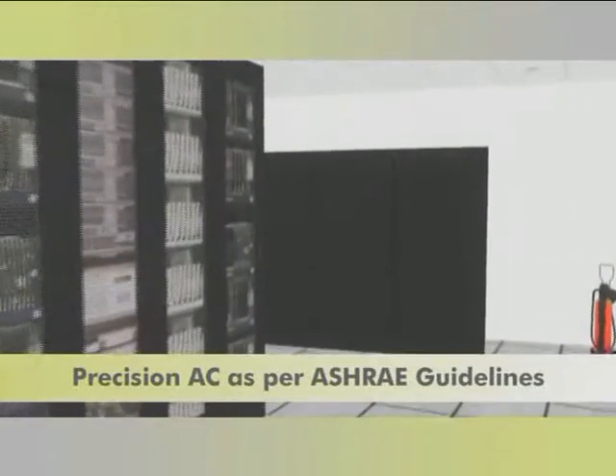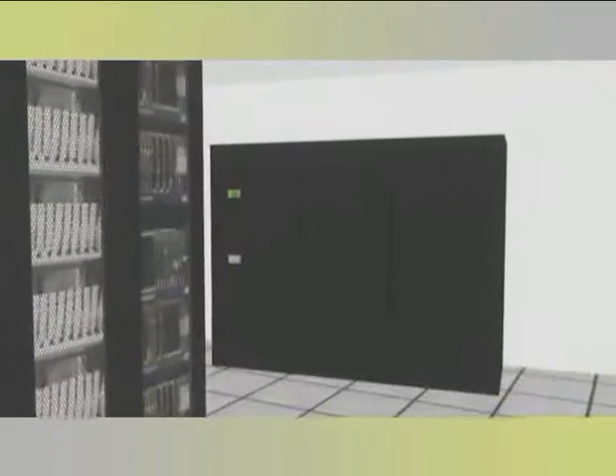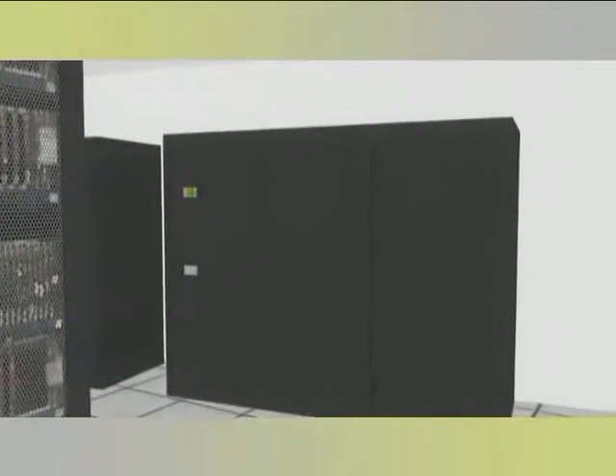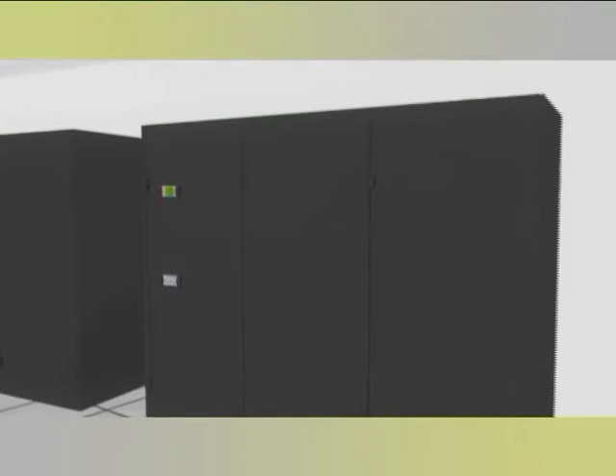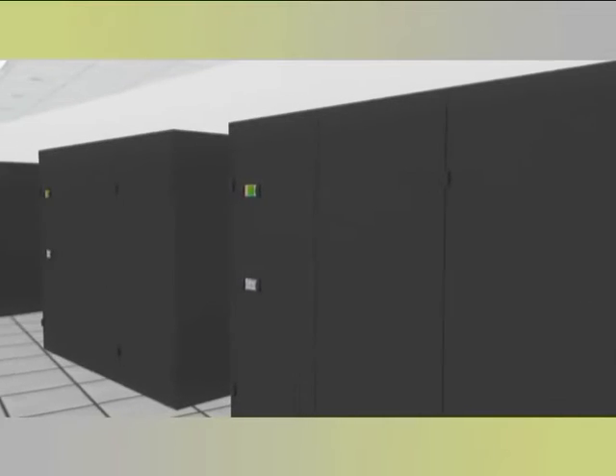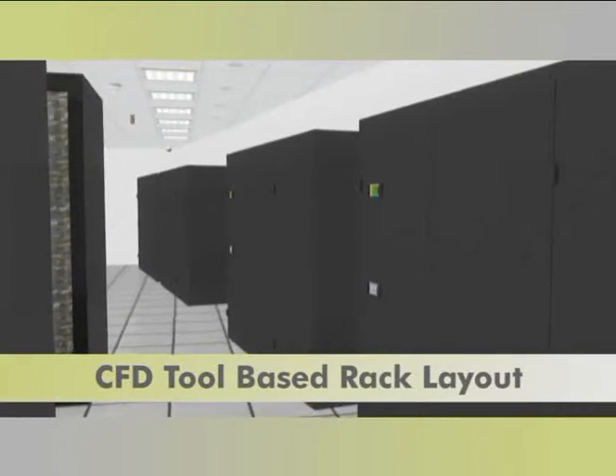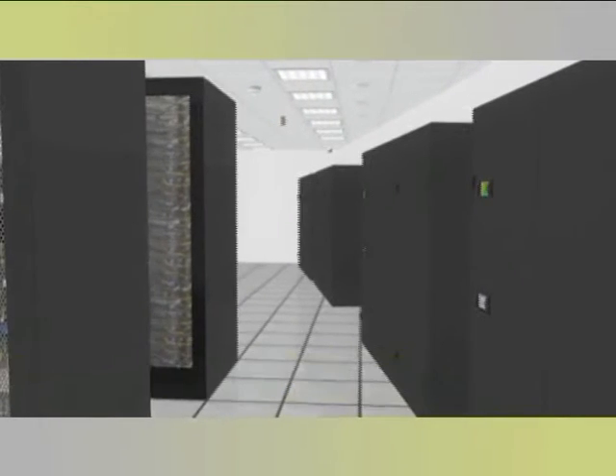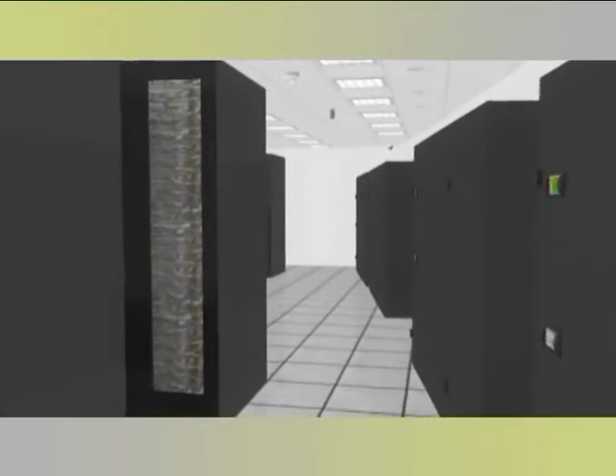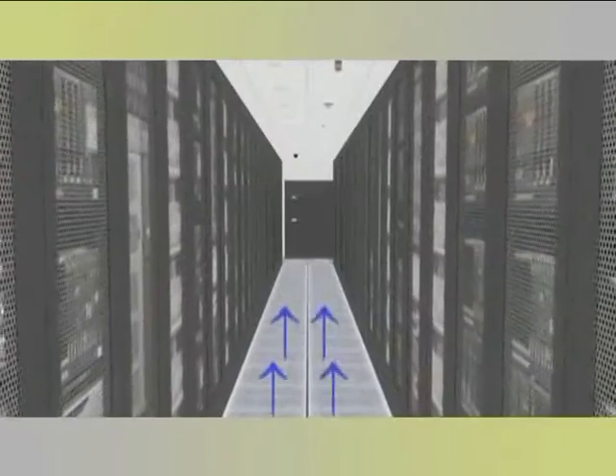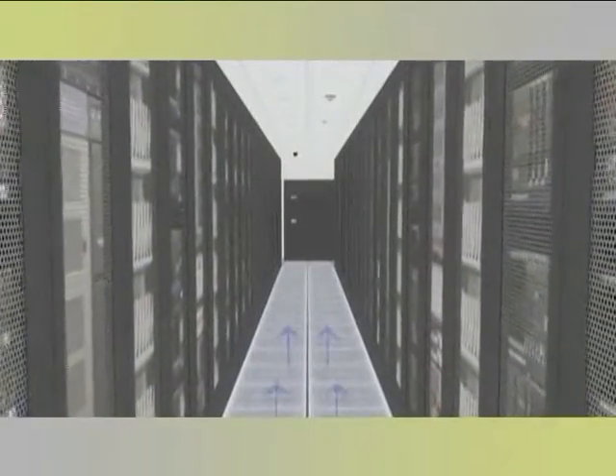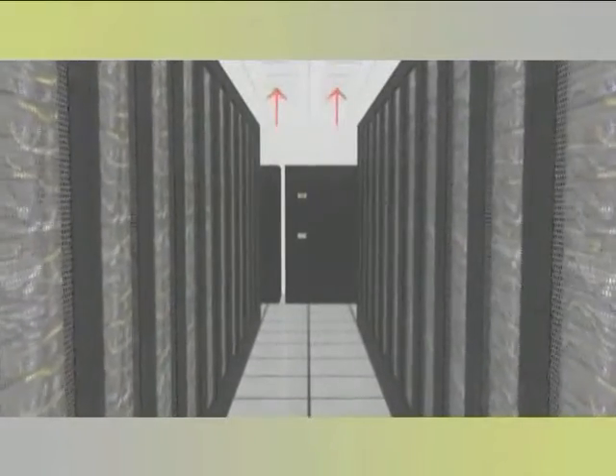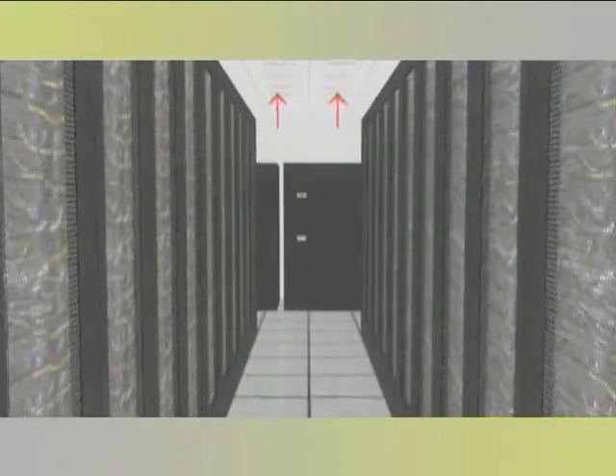Highly redundant precision air conditioning systems with dust control environment have been installed in the Airoli data center. The rack layout design in the server halls is based on CFD tool to ensure optimized airflow to all the racks. In the cold aisle, air rises through the perforated floor tiles, and in the hot aisle, air returns to the AC units through the perforated false ceiling.